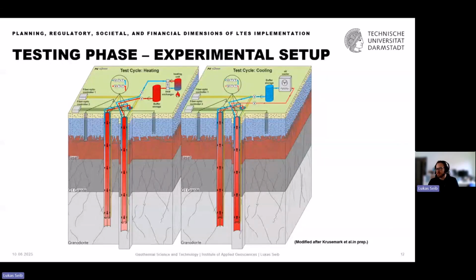And this was basically how these experiments looked like, a little bit confusing, but basically we have our 3 boreholes here. They are all connected to a heating unit with a heat exchanger, and we basically pump the fluid through the boreholes, through the heat exchanger, heated up into a buffer storage, and then back into the borehole. All of these experiments were monitored with temperature sensors on the wellhead and volume flow sensors, of course. And in the inner pipe, in the outer pipe, and in the grout of the borehole, we had fiber optic cables to also measure the temperature variability over the depth for each heat exchanger. And everything was also monitored in these groundwater monitoring wells, at least in the upper section. During the cooling cycles, we basically cooled the whole thing with an air cooler.